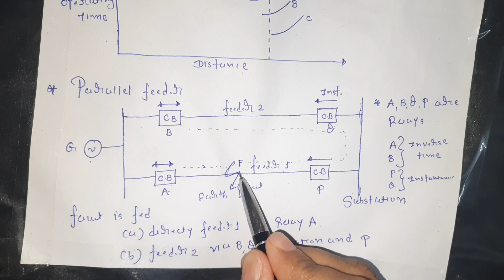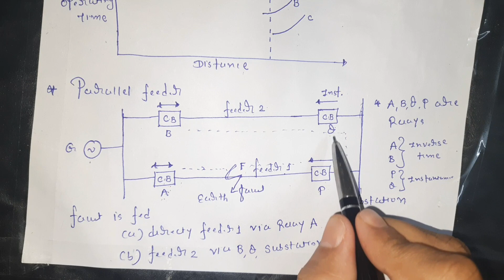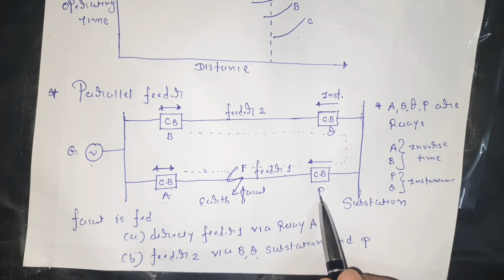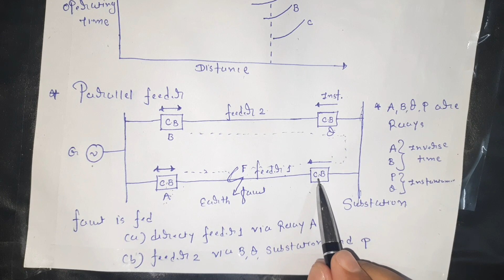Now what happens when the earth fault occurs here? Power flow in this section BQ is in the right direction. So the relay at Q will not operate. But the power flow in P is in the reverse direction. So that is why relay P will operate. And as I have mentioned, the characteristic of the relay at P is the instantaneous type. So the relay at P will operate instantaneously and trip this circuit breaker.